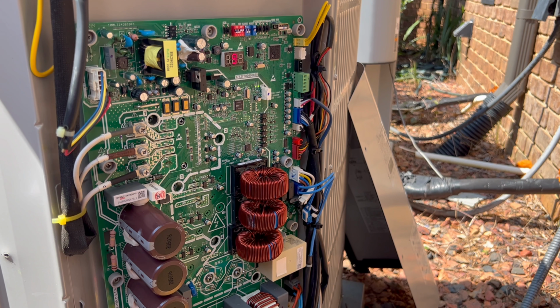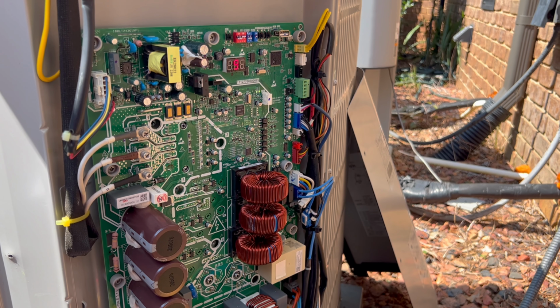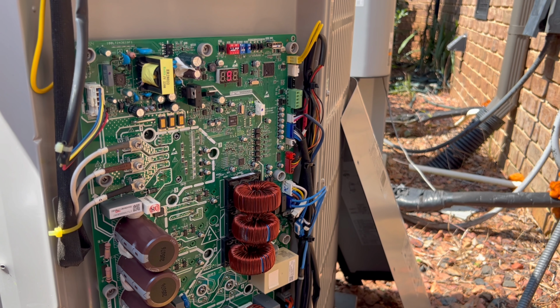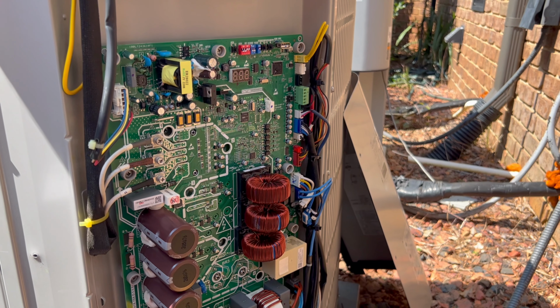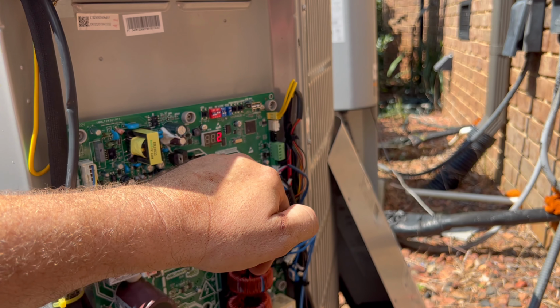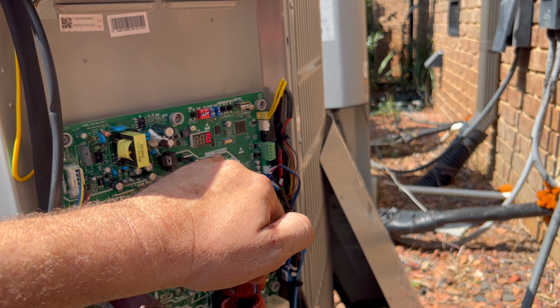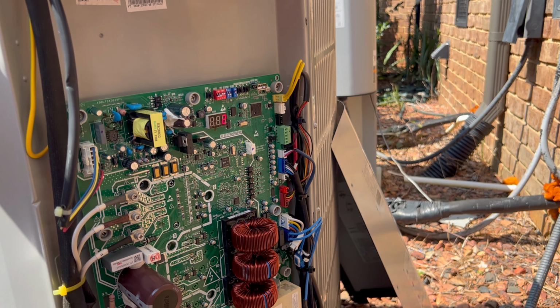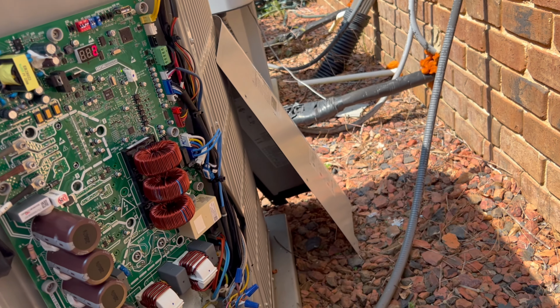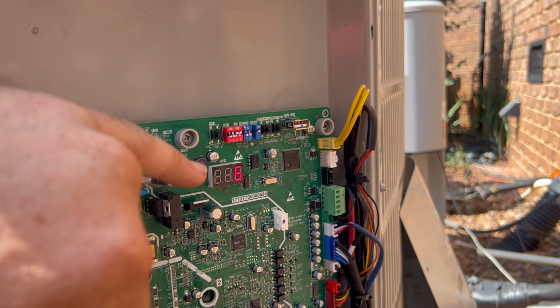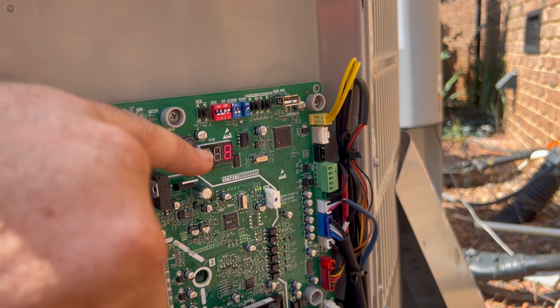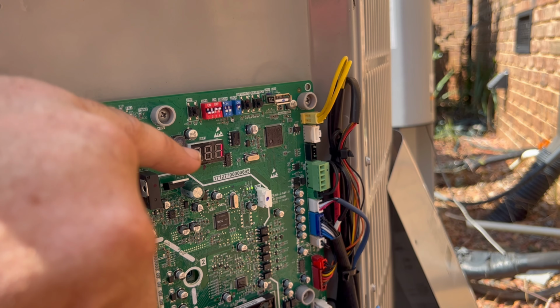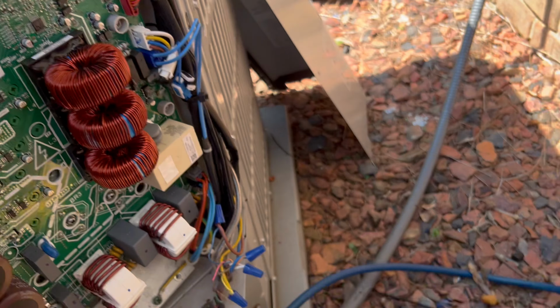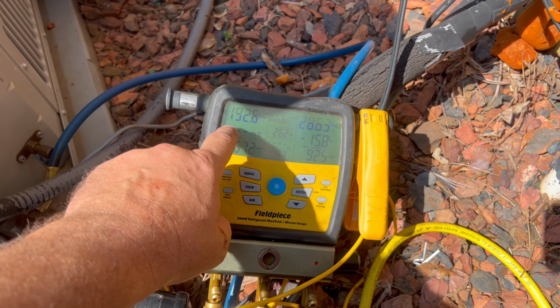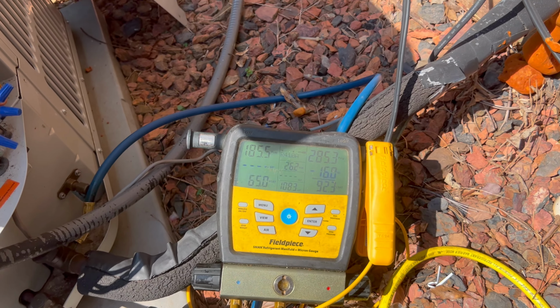What this guy's doing is essentially checking ambient outdoor temperature, coil temperature, and whether there's a call for cooling. Eventually, once that compressor starts up, that 92 degrees where it's showing us our outdoor ambient will change over into essentially a run percentage. As we said, now we're actually operating the compressor. I don't know how it comes out on the camera, but it's going up 10, 19, 20% now, slowly creeping up. You can see correspondingly our pressures are changing, so our inverter is starting.